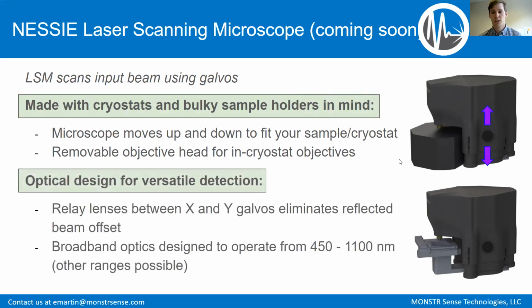The other thing is, none of the microscopes we saw in the market really did the XY galvos well. They just put the galvos really close together, which does give you a little bit of aberrations, but more important for us was that the reflected beam has an offset. We put relay lenses between these 2 galvos. You actually use 2 parabolic mirrors to eliminate that reflected beam offset. Our optics are also designed to operate between 450 and 1100 nanometers.